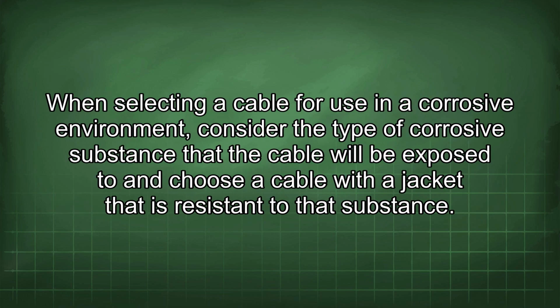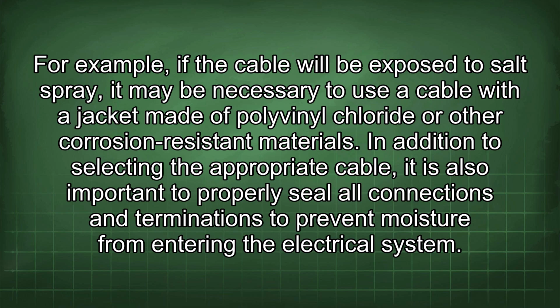When selecting a cable for use in a corrosive environment, consider the type of corrosive substance that the cable will be exposed to and choose a cable with a jacket that is resistant to that substance. For example, if the cable will be exposed to salt spray, it may be necessary to use a cable with a jacket made of polyvinyl chloride or other corrosion-resistant materials.